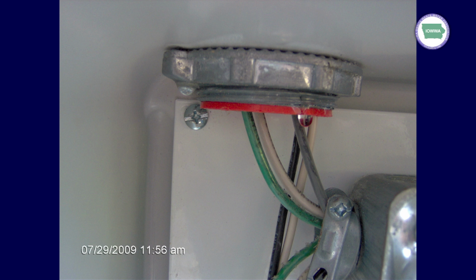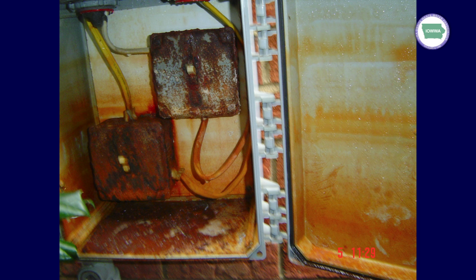Here's another picture of the inside of a panel. Same deal. There was no gasket on the exterior side of the control panel penetration or the fitting. You can see we got water leaking down into the control panel, which is the last place in the world we want moisture or water. Guess what? The inside of the panel is not going to look very good a couple of months down the road if we've got moisture building up inside the enclosure.